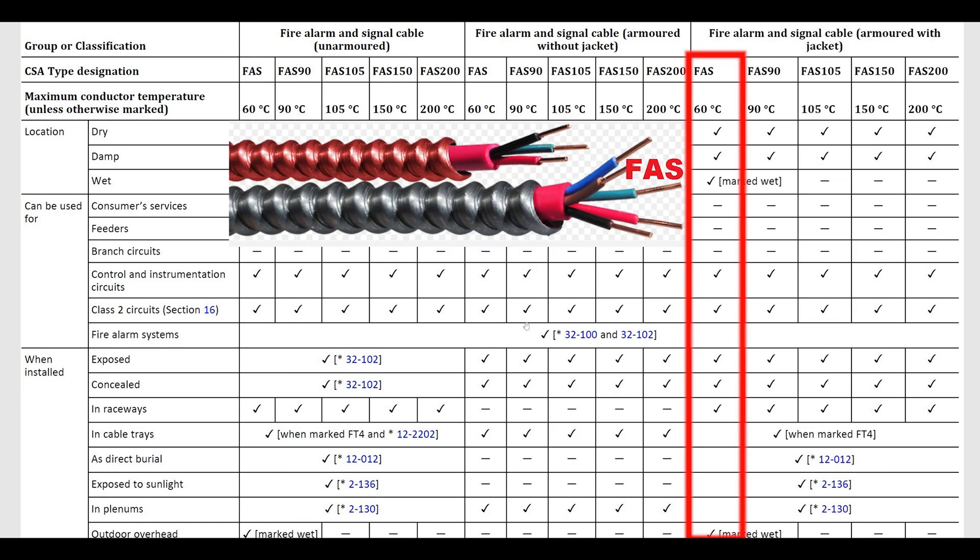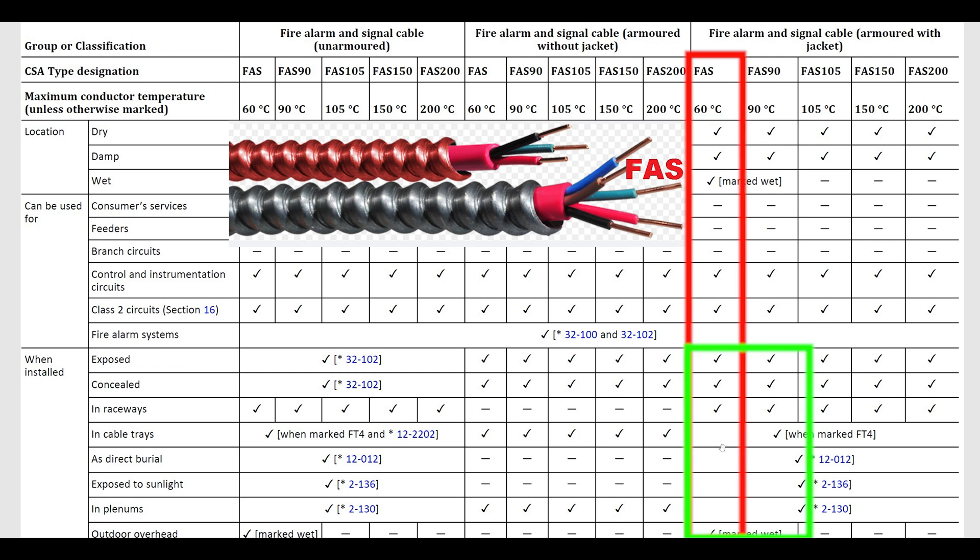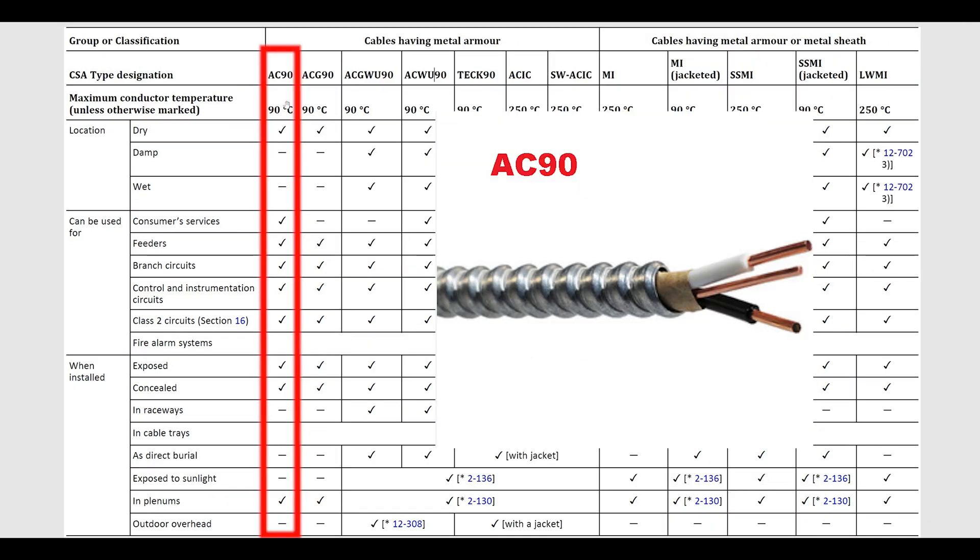Moving on to AC90, one of the most common styles of cable—cables having a metal armor. This is AC90. This is used to maybe feed your furnace or you're gonna see this used a lot in commercial settings for lighting and stuff up in the ceiling. Not good for sunlight or burial though. Also not to be pulled in raceways.